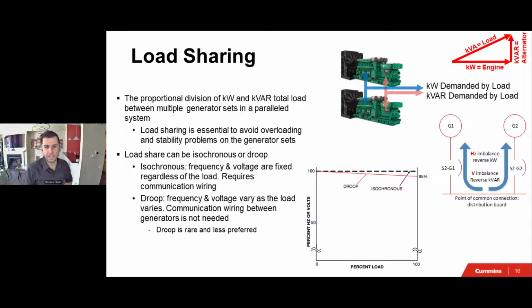If you look at this drawing here with the two generators on one line, with the hertz imbalance and voltage imbalance, if we don't share the load equally or have some kind of smart mechanism to handle that, the generator with the higher power will be pushing the other one. And it will cause it to shut down on reverse power. So we want to make sure that we have effective means to do load sharing.